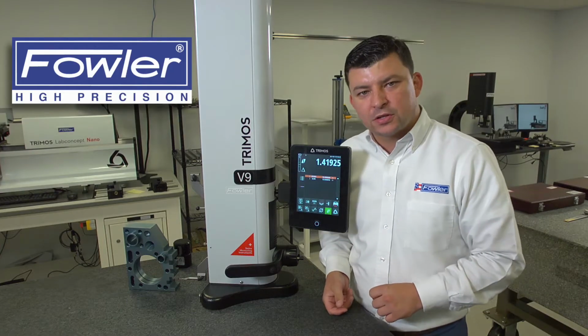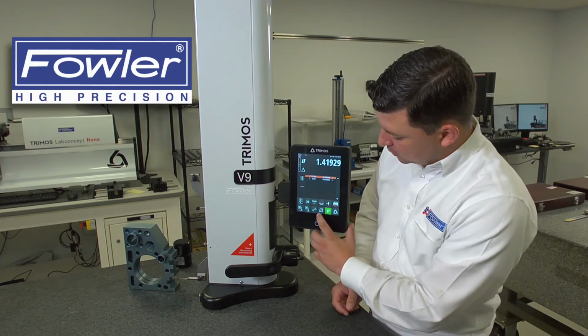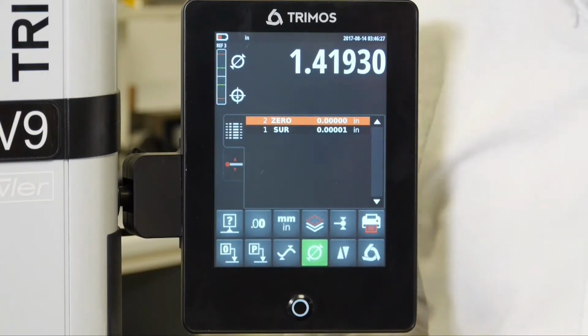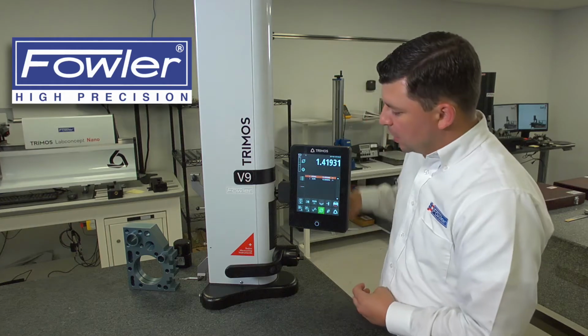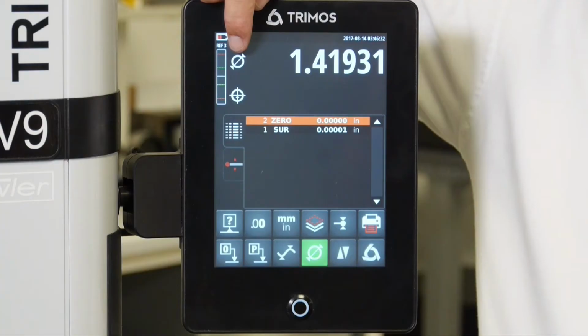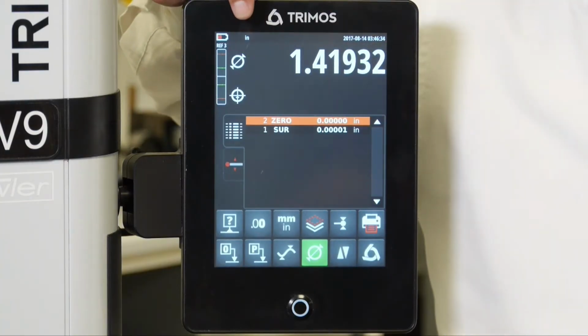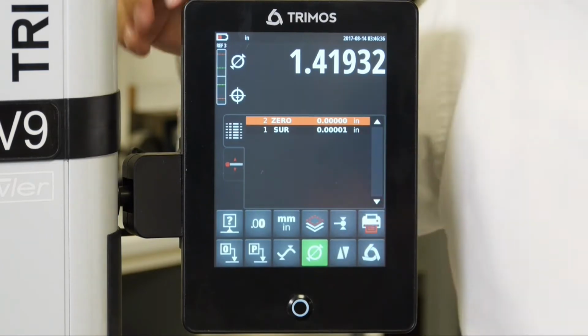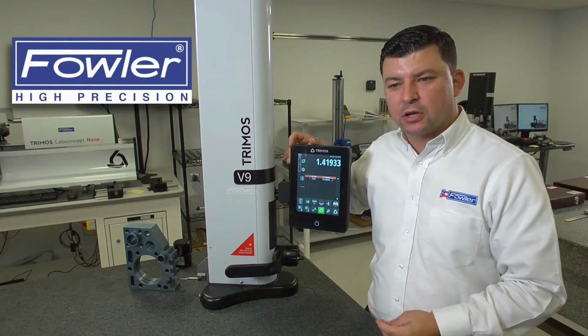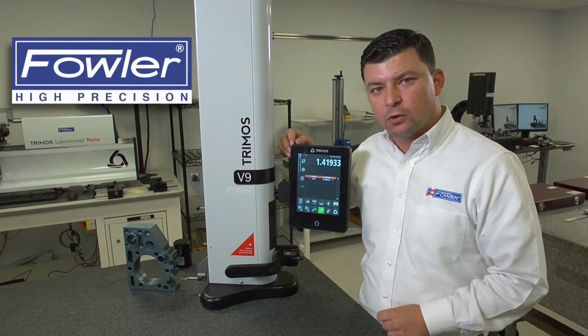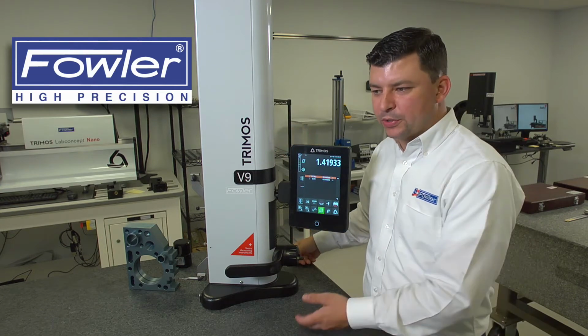From there we can turn on diameter mode. Diameter mode is the little diameter symbol button on the bottom of the display. In diameter mode, you'll notice that you're always going to see a diameter as your top number and a center line as your bottom number. Your center line is always going to be the distance from the center of the hole to your 0 position, where we just set from the plate.